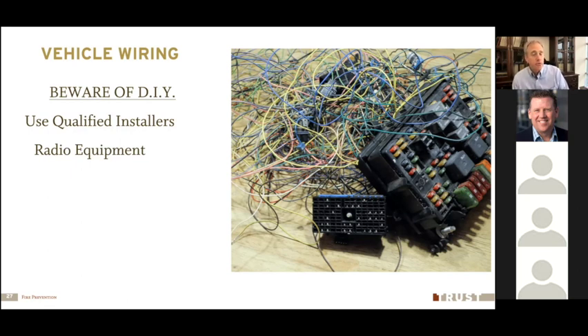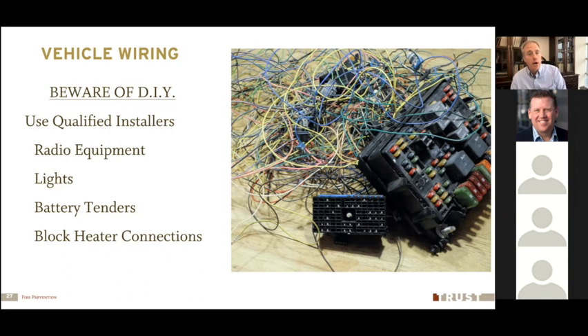We saw an example a couple of years ago of a snowplow catching on fire in a snowplow shed, and it burned up the other snowplows as well as the building. And so often it may be radio equipment, lights that are added to the vehicle. It could be battery tenders that we're using, or block heaters. Often we will add a block heater to a piece of diesel equipment, or we'll replace the connection end on the wire going to the block heater. Again, we need to make sure that we have qualified individuals doing any of these repairs or additions to this equipment, because we have seen just catastrophic losses from miswiring of simple items that are on our vehicles sometimes. So be very careful with that.